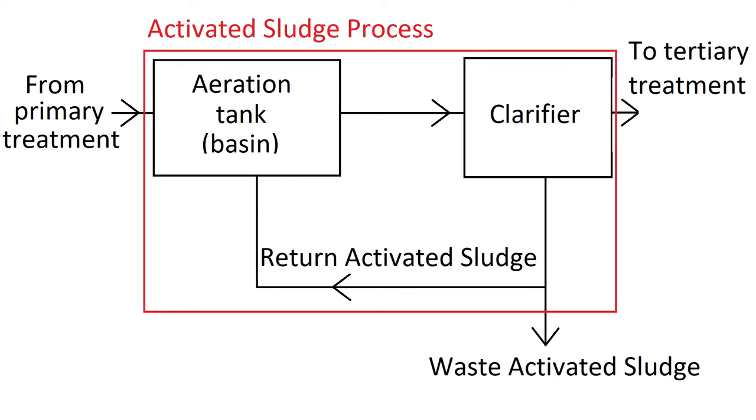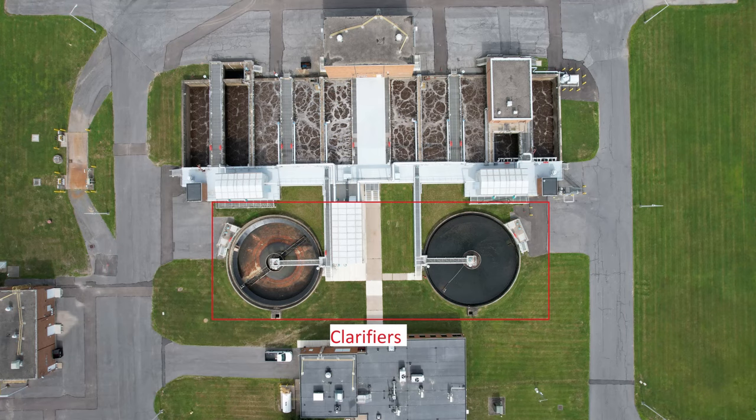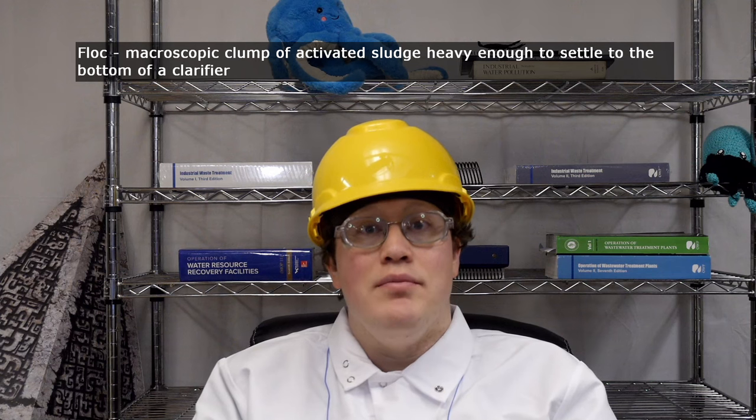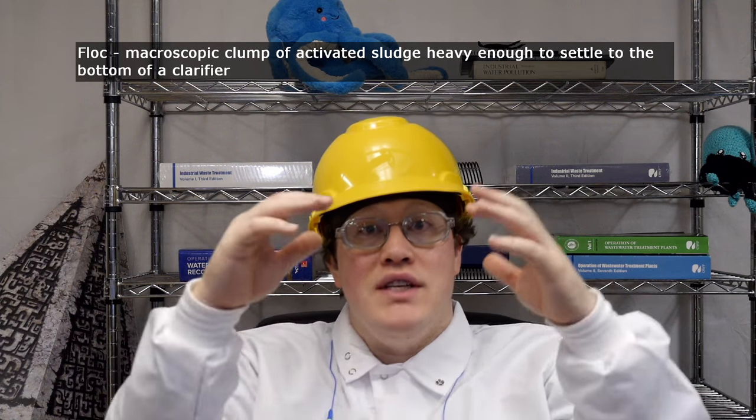After the aeration tank, the mixed liquor is pumped to another tank called the clarifier. There's no air or mixing in this tank because its purpose is to separate the activated sludge out of the water — and the way that's done is to do, well, nothing. If you have the right bacteria active in your sludge, they will glom together into macroscopic clumps called flocs in a process called flocculation. These flocs are heavy enough to sink to the bottom of the tank if the water is still, leaving a clear layer on top — from which the clarifier gets its name. The clear water gets pumped out and on to the next phase of treatment, usually some form of disinfection before it gets discharged to the receiving waters.